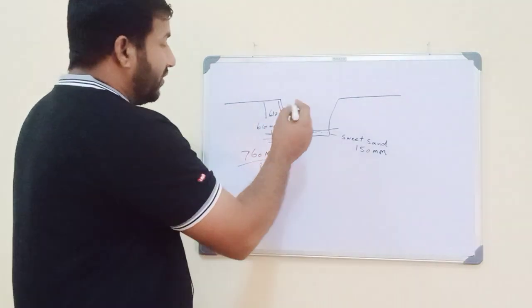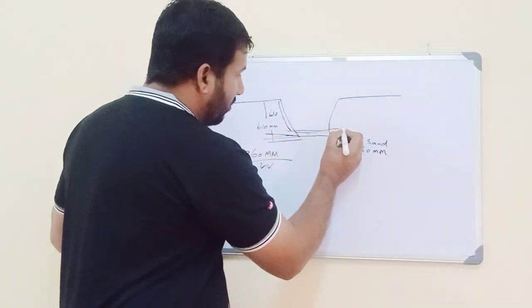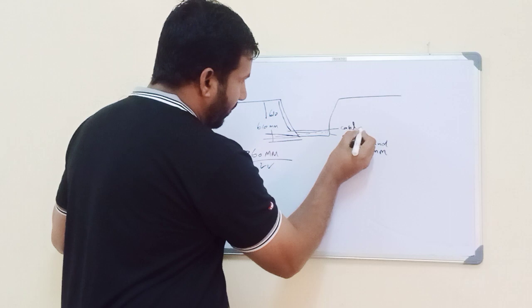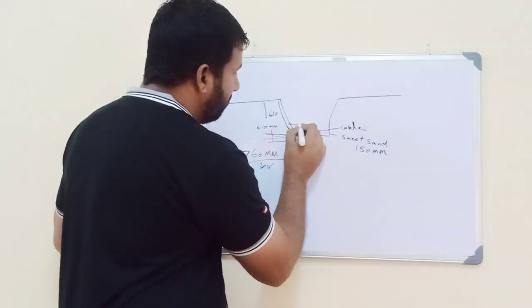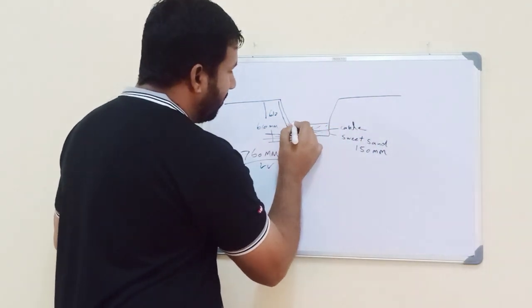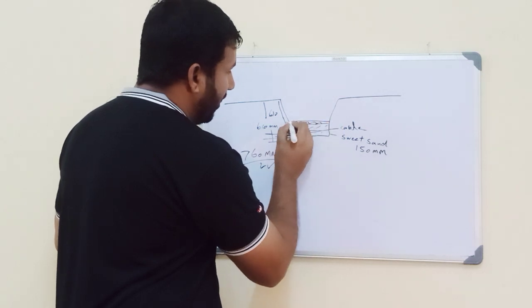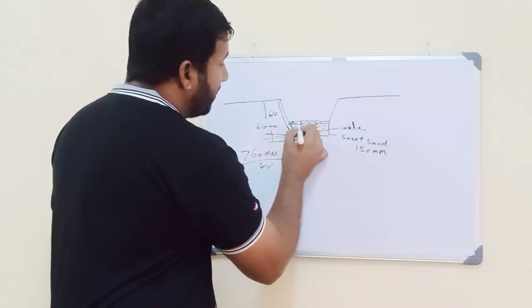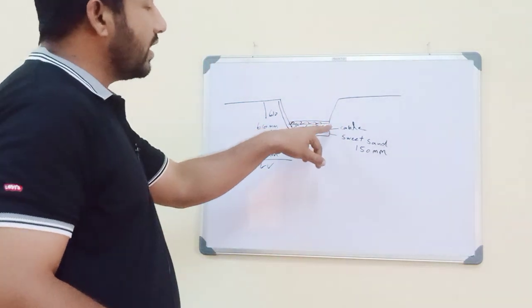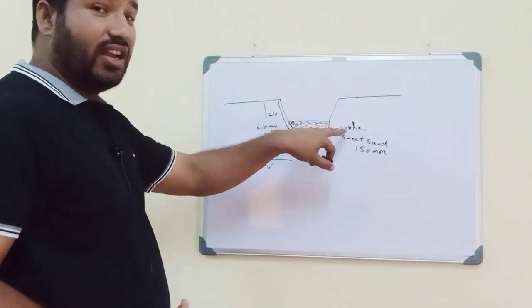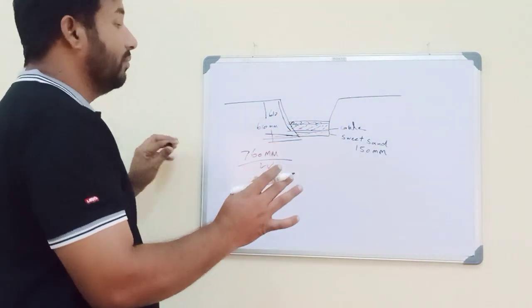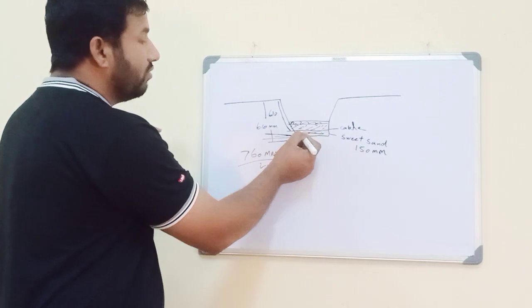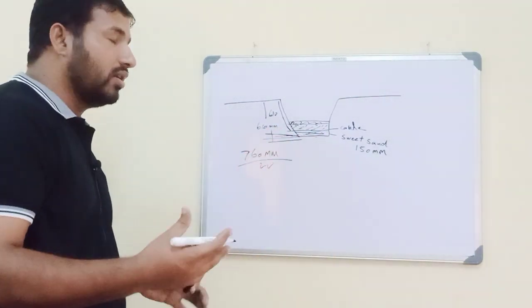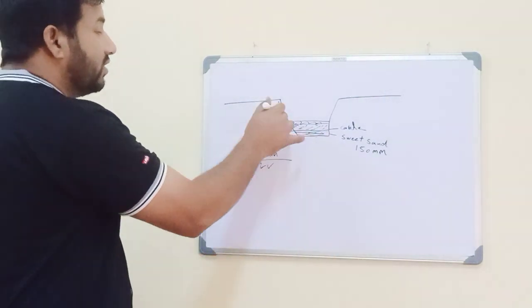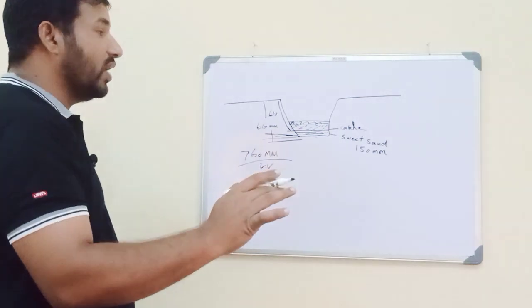After that, this cable - then you have to add 300 mm of sand again, sweet sand. This 300 mm sand, in SABIC, non-industrial areas, or Aramco, is everywhere the same. Only below the cable there is a little bit of difference. Above the cable, 300 mm is required.